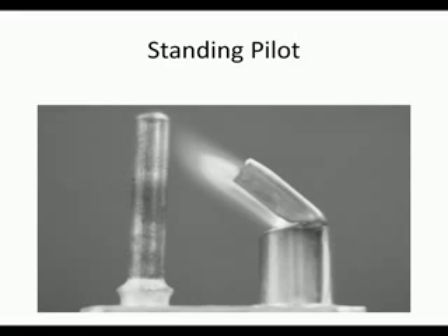First type of ignition we need to talk about is standing pilots. The standing pilot units are used to ignite the gas at the main burners on a conventional gas unit. The pilot flame burns at all times. The pilot flame impinges on the thermocouple, and if the pilot goes out or is not performing properly, the thermocouple will sense this and stop the gas flow through the valve.